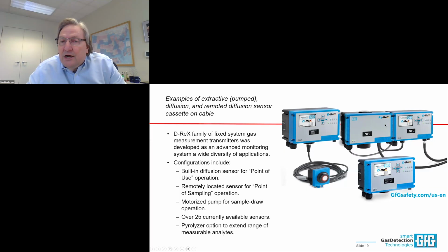Yet another way, the unit in the center has a built-in motorized sampling pump. So we are hooked up to an inlet tube and an outlet tube. The outlet tube can send the sample, after we've measured what's in it, either up the chimney, through a filter bed, or back into the process line where we took the sample to begin with. And that's called an extractive type of sampling system.